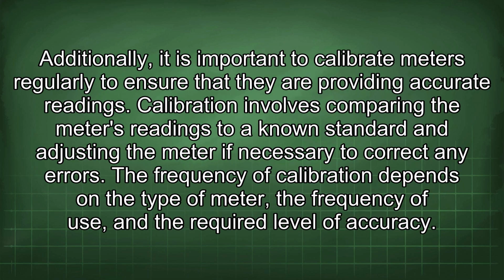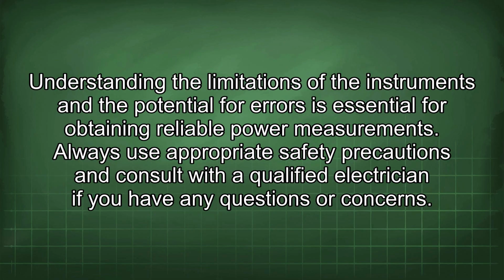Additionally, it is important to calibrate meters regularly to ensure that they are providing accurate readings. Calibration involves comparing the meter's readings to a known standard and adjusting the meter, if necessary, to correct any errors. The frequency of calibration depends on the type of meter, the frequency of use, and the required level of accuracy. Understanding the limitations of the instruments and the potential for errors is essential for obtaining reliable power measurements. Always use appropriate safety precautions and consult with a qualified electrician if you have any questions or concerns.